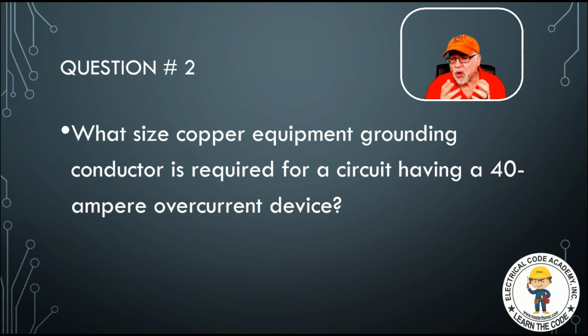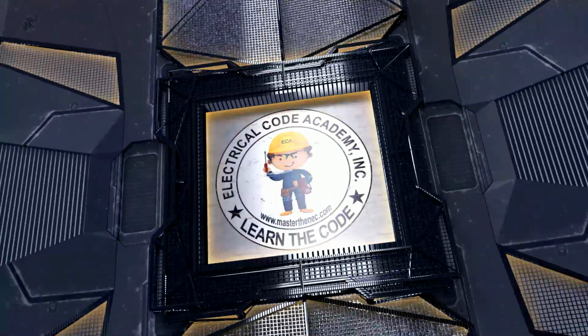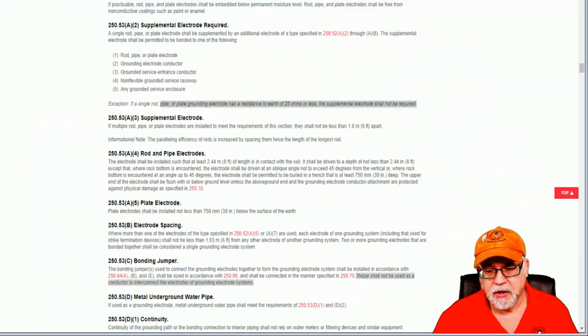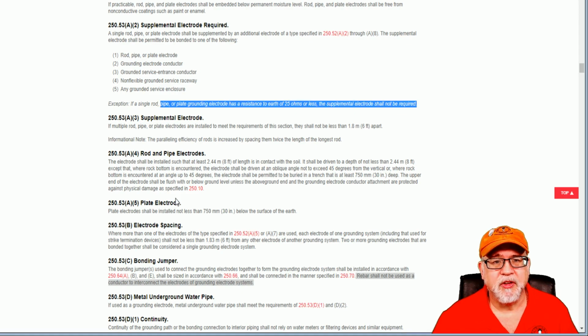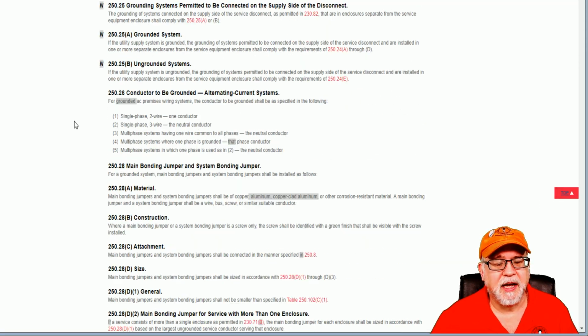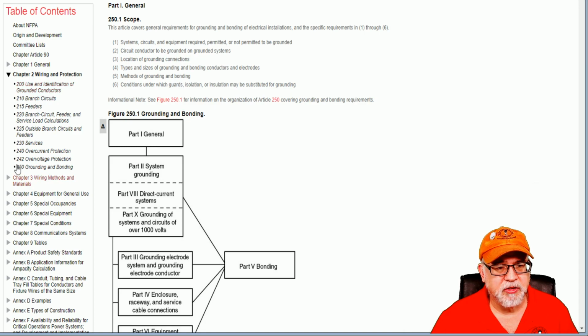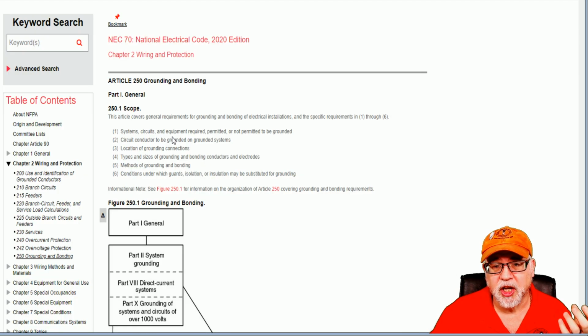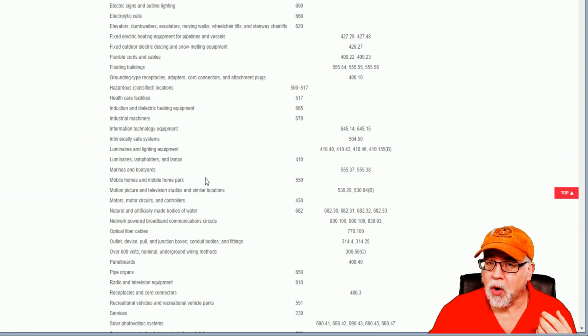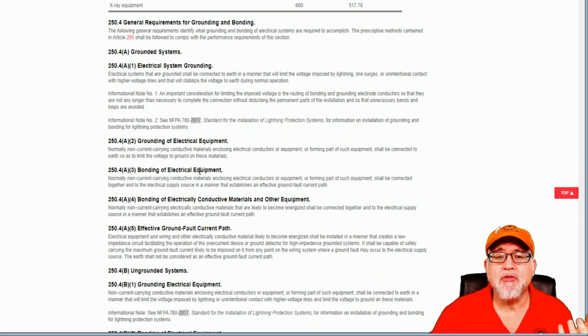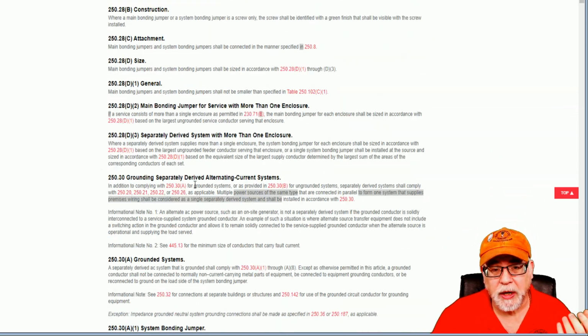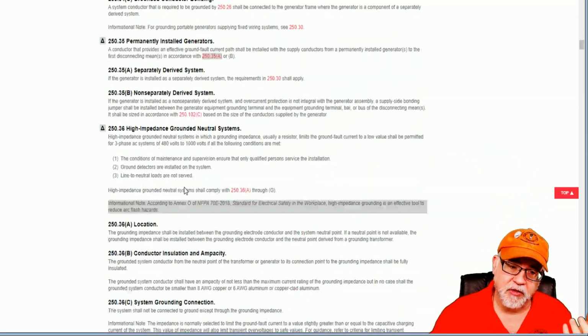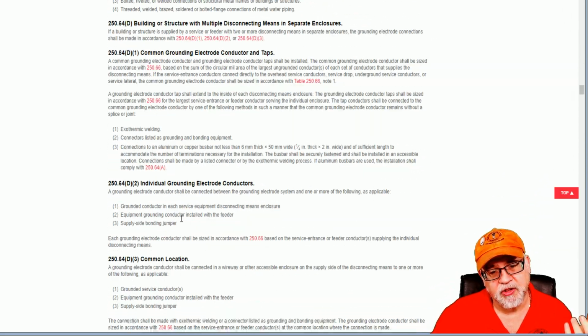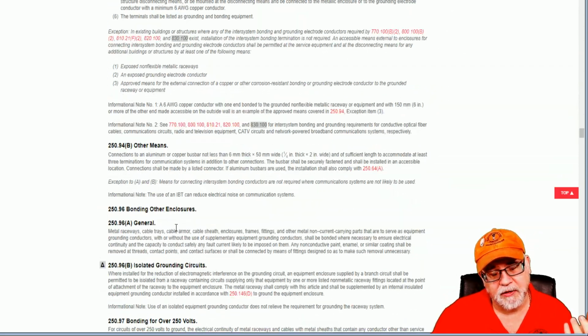Okay. So this is one of the questions in the program. So we want to go back to the code, and we're going to say it's a 40 amp overcurrent device and it's an equipment grounding conductor. So here we are. Now, of course, what we're going to do is go to the top, and we know that we're in 250, and you could go to the index. Or if you're savvy and you know that 250.122 is dealing with equipment grounding conductors, I'll just scroll on down here.